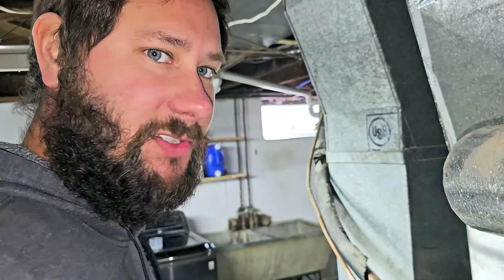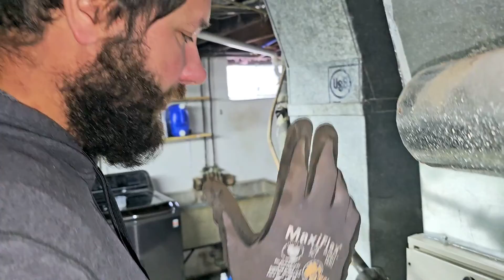This is 7/8 right here. I don't know why they use 7/8. You don't need 7/8 for a 3-ton unit. Anything 3.5 ton and above needs 7/8 for a suction line or vapor line. But for a 3-ton, you should be using 3/4 and 3/8. I don't know why, there's no telling.